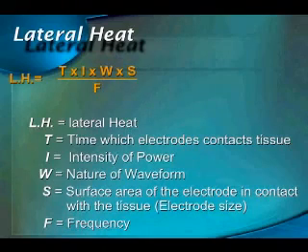Lateral heat relationships: LH equals T multiplied by I multiplied by W multiplied by S, below that is F. Lateral heat could also mean lateral damage. T is related to time, so if you keep the probe to the tissue for a long time, you are spreading lateral heat. If you increase the power, you'll get more lateral heat. The waveform matters. If you use the filter cut, you get less lateral heat. But if in coag mode, you get more lateral heat.